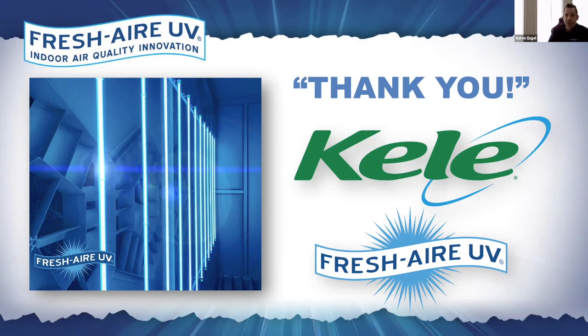And then just change the lamps in a timely manner. If it's every 2 years, do it every 2 years, because the lamps are going to last. The lamps are not going to just stop working after 2 years. They could last for 4 years, 5 years, who knows? But the ultraviolet light does decrease with age. And after 2 years of operation, it has reached a point where you should be replacing with new lamps.